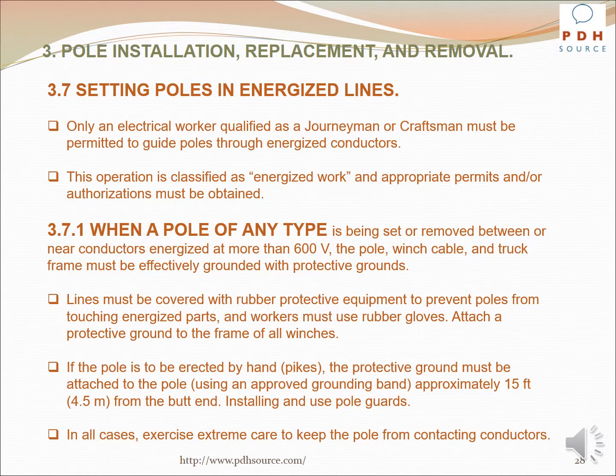Only an electrical worker qualified as a journeyman or craftsman must be permitted to guide poles through energized conductors. This operation is classified as energized work and appropriate permits and/or authorizations must be obtained. When a pole of any type is being set or removed between or near conductors energized at more than 600 volts, the pole, winch cable, and truck frame must be effectively grounded with protective grounds.